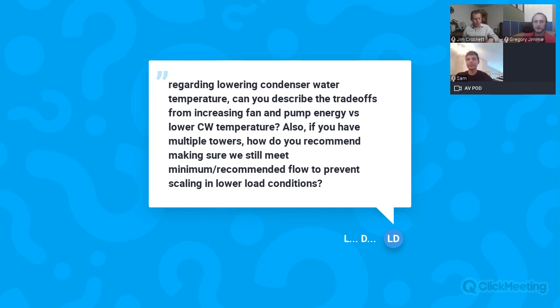So in terms of finding the trade-off, one thing it's important to remember is that with chillers, as the temperature changes, there's a linear response for chillers. On the pump and fan side, there's an exponential response. So for example, as you increase your tower speed from 50% to 100%, there's roughly an 8-fold increase in power consumption. At the same time, when you go from 50% down to 40%, there's very little additional improvement, you're already at the flat part of your exponential curve.